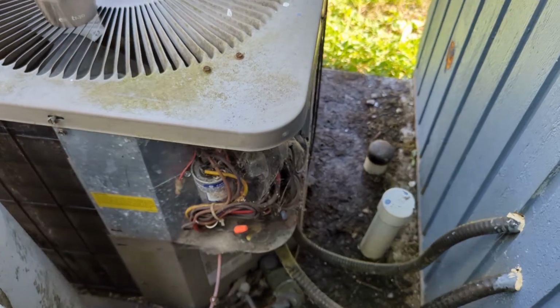So the day we replaced the condensing unit, we did not complete the installation because we wanted to make sure that pressure switch was the only source of the leak in the heat exchanger, that there was no other leaks, that we didn't just get excited about the one leak. We just had to confirm that before we went through the motions of completing the installation.